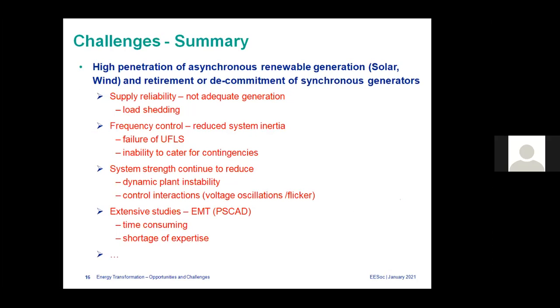The other one is inability to cater for contingency. Multiple contingency is a major issue. You might have heard that we had the blackout in South Australia maybe about 3 years ago, where they had a number of faults in the system because there was a severe thunderstorm, and a number of wind farms tripped as a result, because wind farms struggle to keep stable operation, so they tripped. As a result, there is one interconnector from Victoria to South Australia. The power flow on that interconnector significantly increased, so it tripped as well. But the remaining system had under frequency load shedding, but the power imbalance was too much. The frequency drop became very severe. So the whole system became black within a few seconds. So catering for multiple contingencies could be very challenging if you don't have enough inertia in the system.